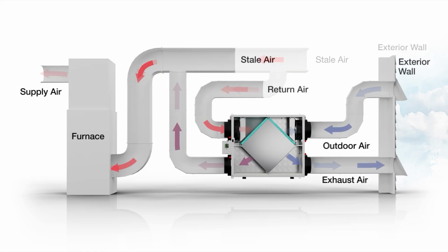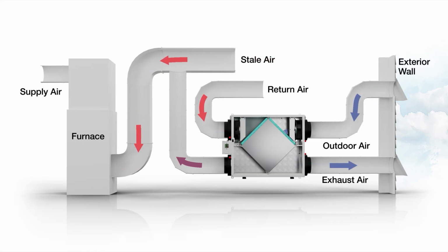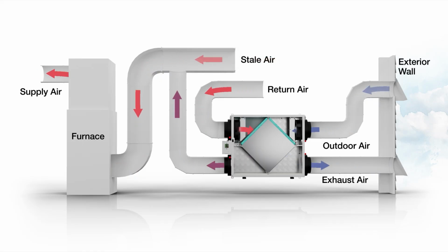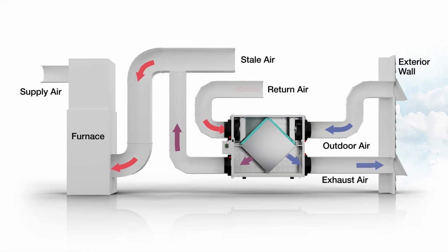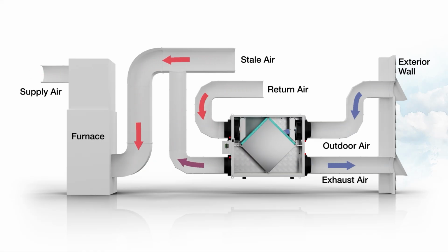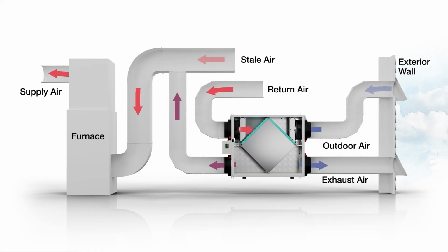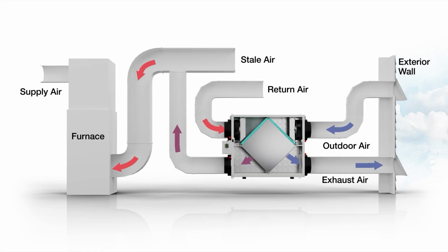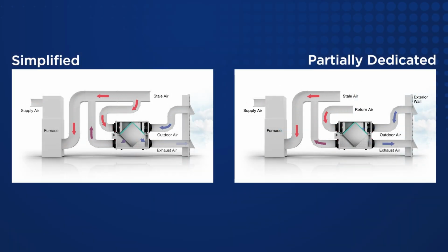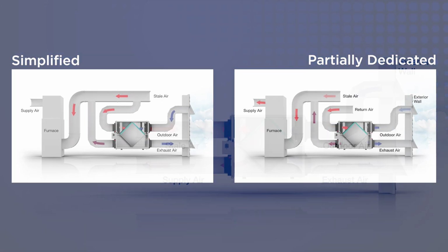A partially dedicated installation draws stale air from specific locations, such as bathrooms or laundry rooms, and introduces fresh air into the cold air return. This method allows for targeted ventilation of specific areas. For both the simplified and partially dedicated installation, while not required for the ERV to run properly, interlocking the air handler with the ERV will allow for even air distribution.